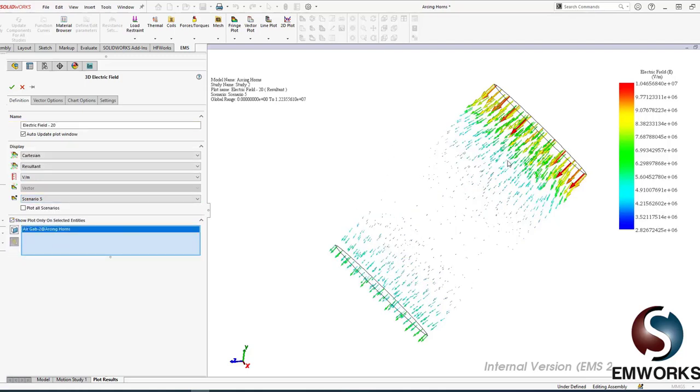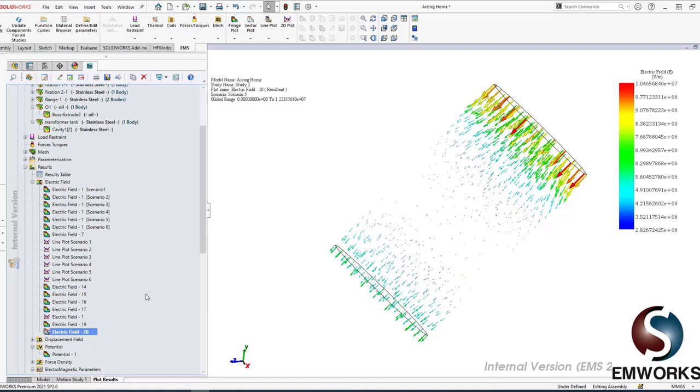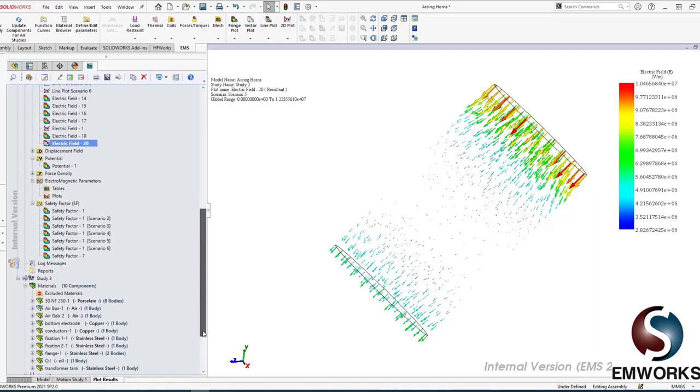So everything is going to break now. So the line plot along with the fringe plot can tell you, so this is good. Let me repeat: you want a design that is not going to produce any arcing at the normal operating condition at 10,000 volts, but you want it to produce the arcing or the corona or the sparking only when there is a fault condition. That's exactly what we achieved for this design.